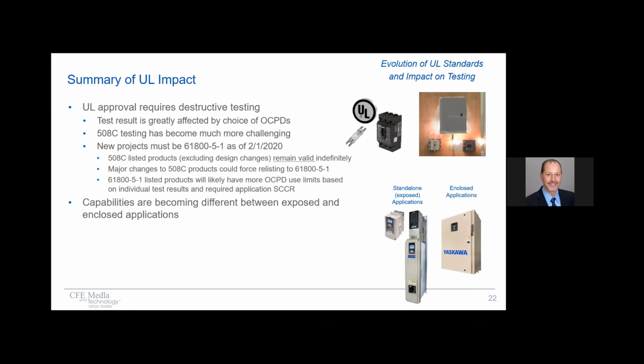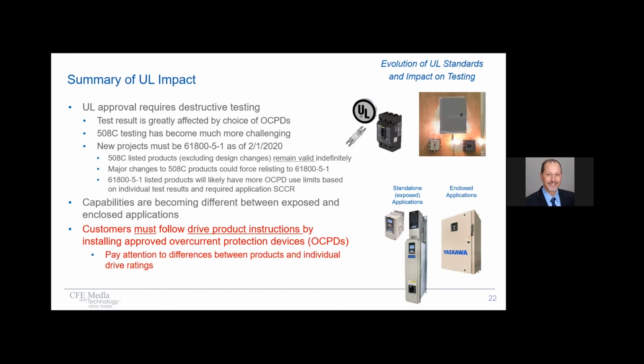Also, capabilities are becoming different between exposed and enclosed applications. So be aware that when you're choosing a protective device, know whether your application is standalone or whether it's a drive that's installed in a supplementary enclosure. There is a difference there in what can be used. And of course, where you'll find that is in the individual product instructions from drive suppliers. So pay attention to all these differences and caveats.